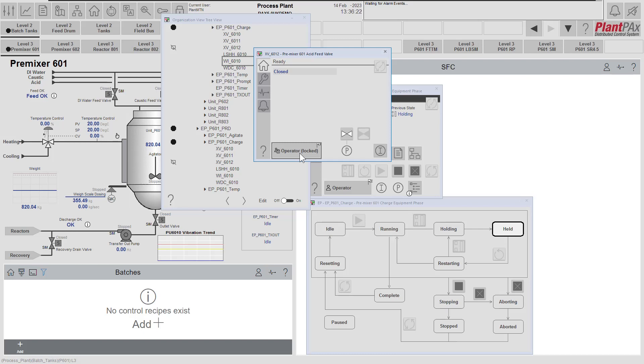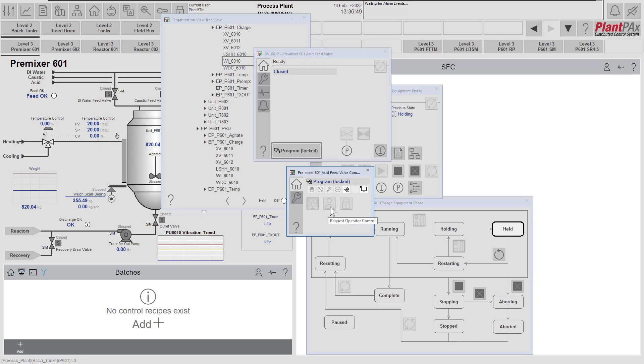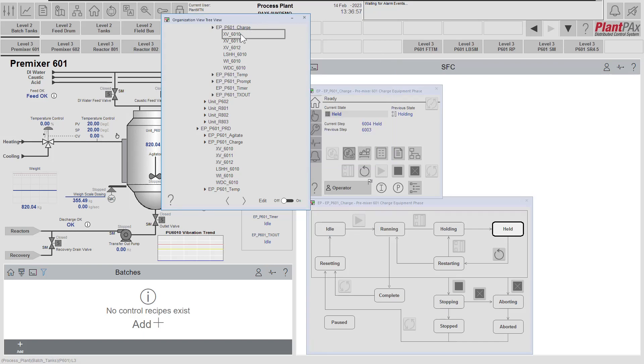From the faceplate we can see that it's locked into operator mode. Locking something into operator mode prevents it from being acquired, so the equipment phase cannot take ownership of this device. This is easy to resolve from the faceplate — we click on the operator status indicator and switch it into operator mode, not locked into operator mode. As soon as we do that, the equipment phase acquiring logic acquires the device, puts it into program mode, and locks it into program mode so the operator cannot put it back. XV6010 is now owned by the charge phase, and the same for XV6011 and XV6012.